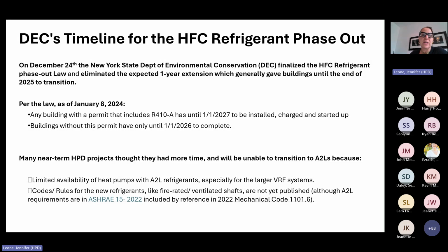A couple reasons for that: there's limited availability right now of equipment with the new A2L refrigerants, and some lack of clarity on the codes and rules for handling these new refrigerants, which are more flammable than previous ones. So we were really concerned. Some folks raised the alarm, and we had to think about what to do for projects that can't transition right now, with near-term closing deadlines and finalized designs.